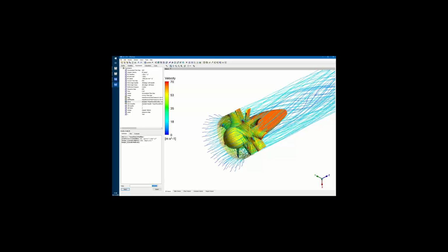If we take a closer look at the total pressure difference of the stage, you can see we only achieve roughly 450 Pascal instead of the 500 Pascal we put in as an operation point condition at the beginning. So we are short of 50 Pascal.